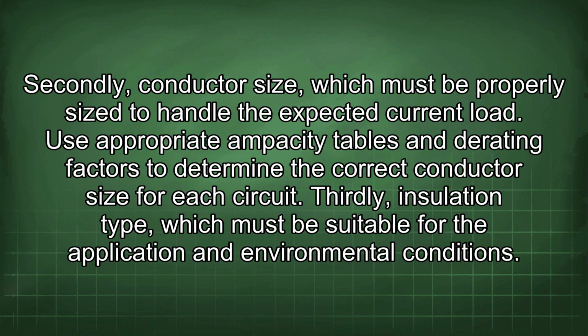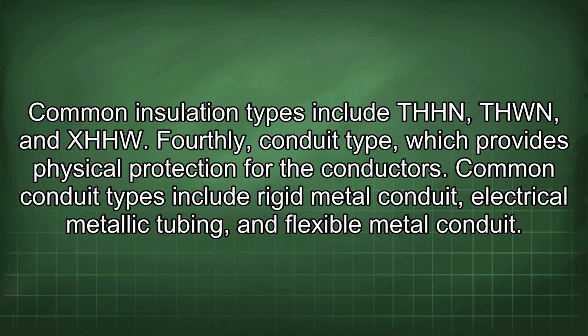Secondly, conductor size, which must be properly sized to handle the expected current load. Use appropriate ampacity tables and derating factors to determine the correct conductor size for each circuit. Thirdly, insulation type, which must be suitable for the application and environmental conditions. Common insulation types include THHN, THWN, and XHHW. Fourthly, conduit type, which provides physical protection for the conductors. Common conduit types include rigid metal conduit, electrical metallic tubing, and flexible metal conduit.